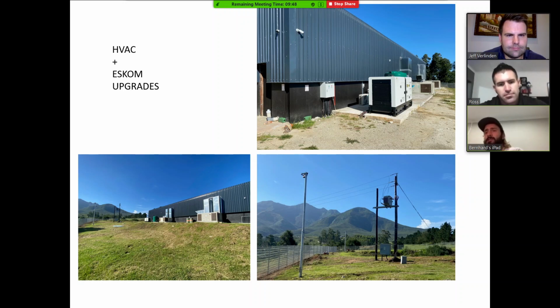Currently that transformer is probably only running at half capacity. That said, it does push 300 amps through the building, and the generator is more than capable of handling it. It's a 125 kVA, which is the minimal requirement, but it's a very high spec generator able to draw 300 amps through it into the main DB without short circuiting the system. That's important to consider when buying a generator - not just its kVA, but its internal specification on how it carries that power through.